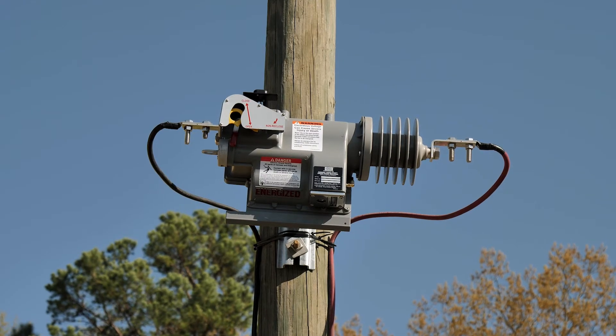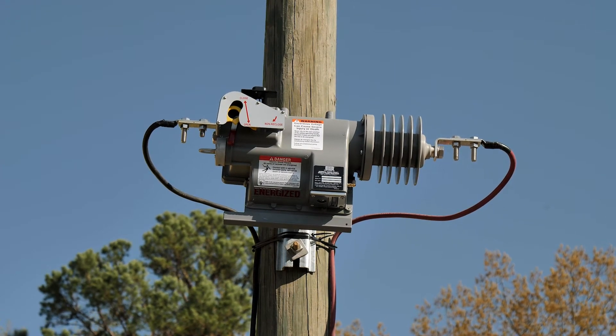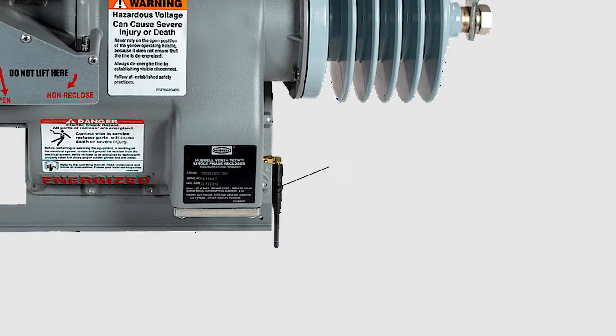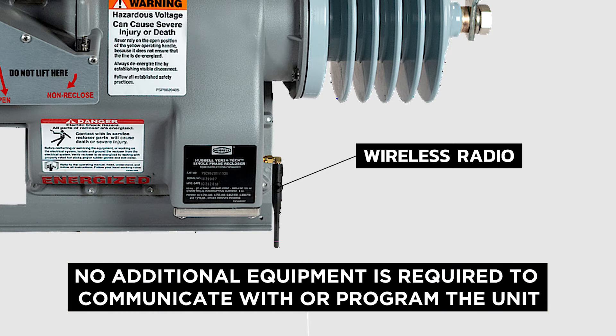After deployment in the field, the user may wish to reprogram the Versa-Tech according to a load change on that circuit. This can be done from the ground via a wireless 900 megahertz or Wi-Fi connection, or remotely via a cellular connection. As the radio and power to broadcast the signal are included in the Versa-Tech, no additional equipment is required to communicate with or program the unit.